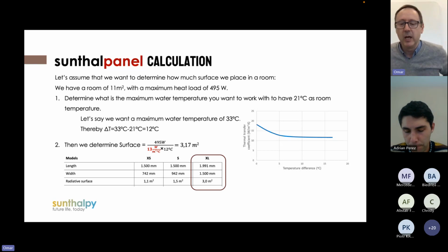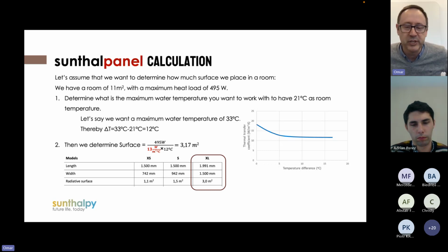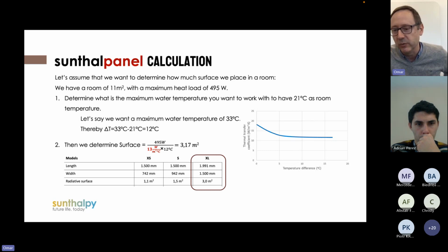Okay, since there's interest, I'm going to get deep into the cooling topic. Of course, you have the dew point limitation. If you have a humidity of 70% and the room temperature is 21, you know for certain that if you pump water at 18 Celsius or below, you will have condensation. In one case, our plates, we know, because we have a customer who installed our plates but didn't install an Ecoforest heat pump, they did it on their own, so we didn't have any control over the heat pump's settings. We told them this project is in a very humid area, so limit the pumping temperature in cooling to above 18 Celsius.